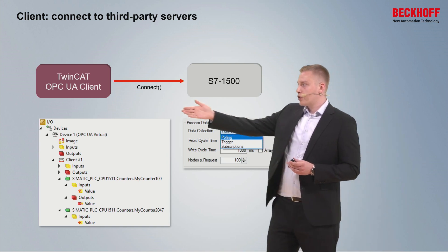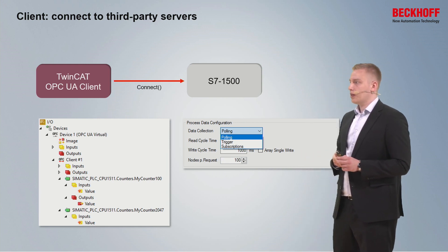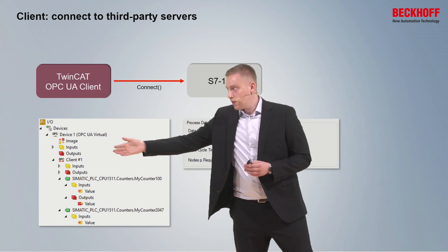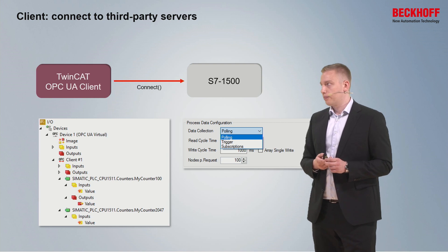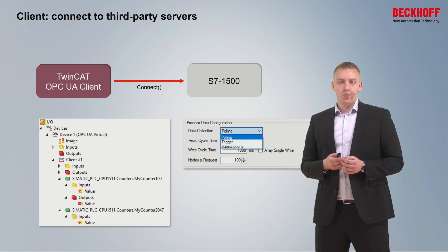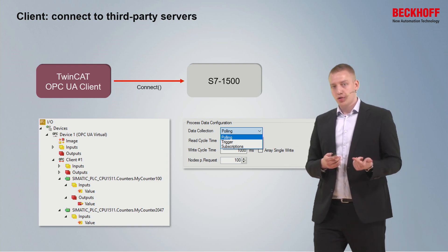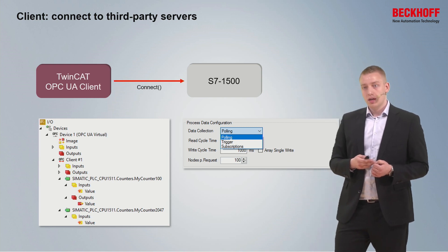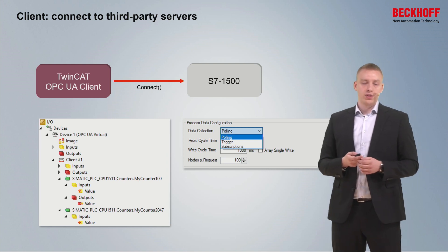An OPC UA virtual device can contain multiple OPC UA client devices, each representing one connection to an OPC UA server. For each client device, there are three ways to configure communication: polling, subscriptions, and triggers. Triggers are helpful for event-based communication, where a specific PLC event should trigger the reading or writing of a variable on the OPC UA server.